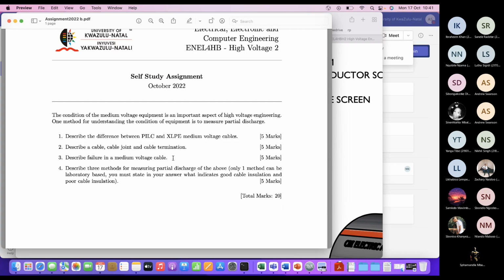Describe the failure in a medium voltage cable. There's a number of things that you could have looked at. I think most people were okay here, or at least I've started giving highish marks here. So the cable, the cable joint, and the cable termination can all fail in different ways. The cable could have a long-term thing where there's a slight defect, partial discharge starts occurring, and it continues to occur until complete breakdown happens.